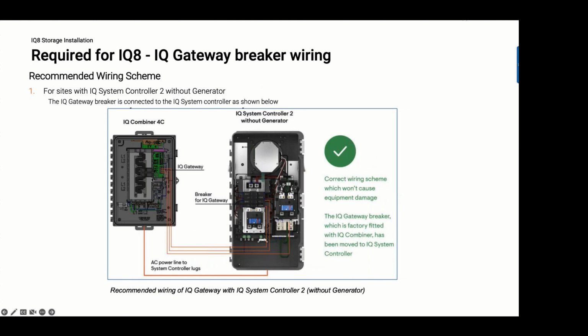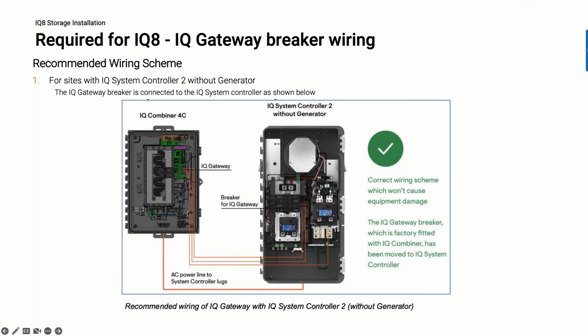To power the Envoy off of the system controller bus, you can relocate the IQ gateway breaker from the combiner, if it's an Eaton breaker, to the system controller generator breaker slot. Just move the circuit breaker from the combiner to the system controller, put it in the generator slot, and run wires directly from the breaker back to the IQ gateway in the combiner to power the IQ gateway. Now, you'll only be able to do this if there isn't any plan to install a generator. Also, if the IQ combiner has anything other than an Eaton breaker, you won't be able to move it to the system controller. So you'll have to find another Eaton breaker replacement for the system controller.